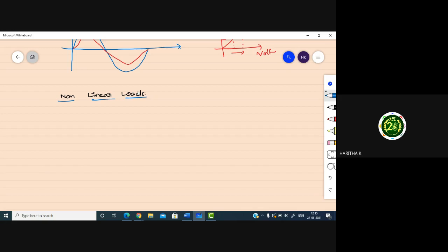All the electrical loads may be either linear loads or non-linear loads, depending on how they draw the current from the main power supply waveform. If the current waveform is following the voltage waveform, then it is a linear load. Otherwise, we have to treat it as a non-linear load. With non-linear loads, the current is not proportional to the voltage and it fluctuates based on the load impedance. Based on the type of load, the current waveform will fluctuate with respect to the voltage, but it won't follow the voltage waveform. Those types of loads are called non-linear loads.